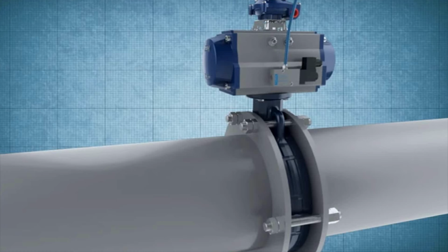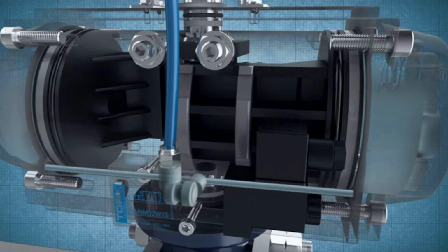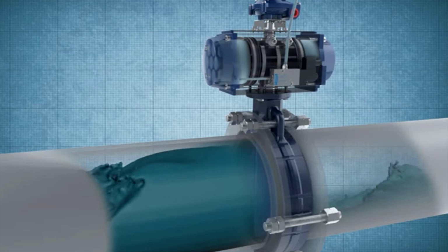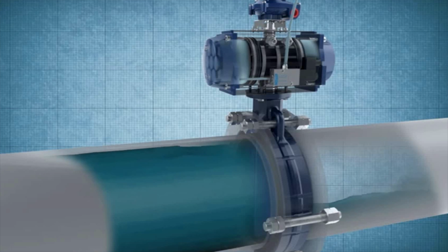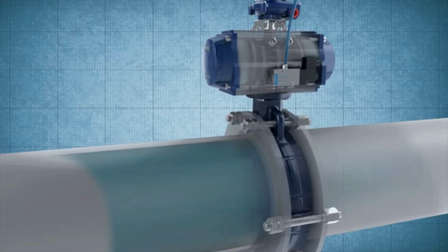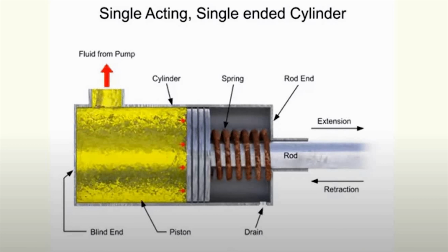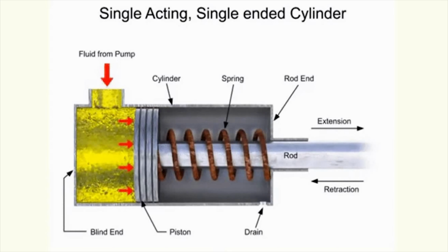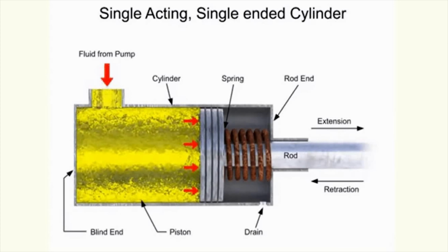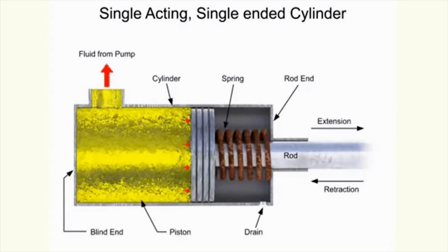The advantage of pneumatic actuators consists exactly in the high level of force available in a relatively small volume. While the main drawback of the technology consists in the need for a compressed air network composed of several components such as compressors, reservoirs, filters, dryers, air treatment subsystems, valves, tubes, etc., which makes the technology energy inefficient with energy losses that can sum up to 95%.